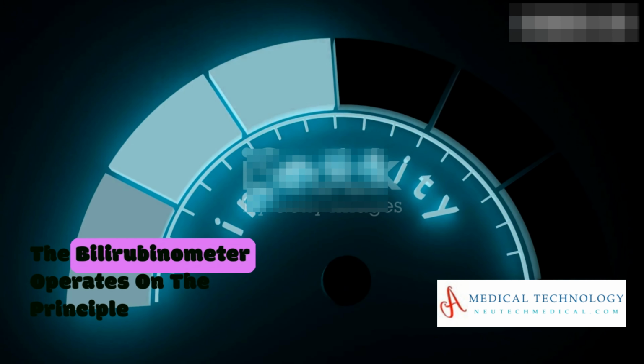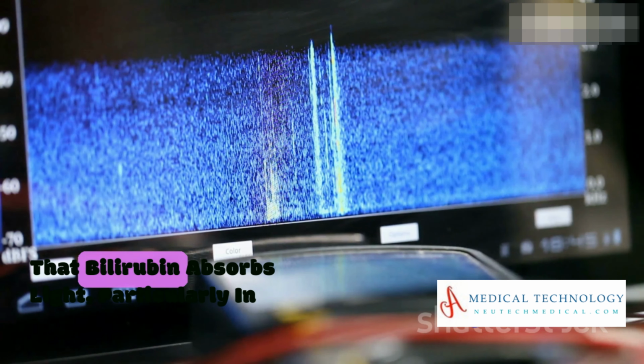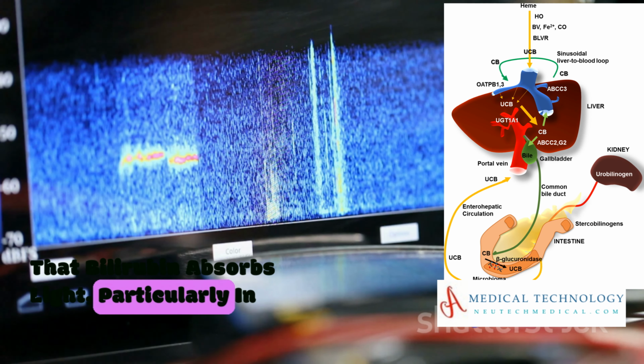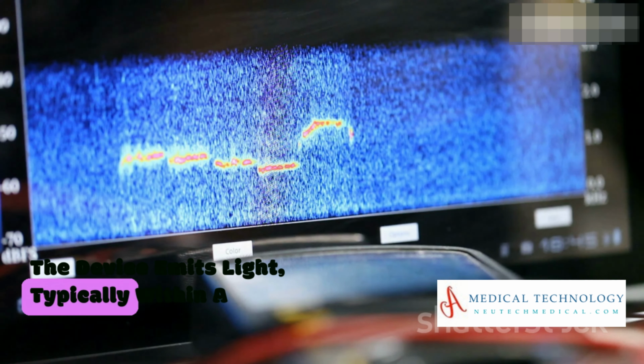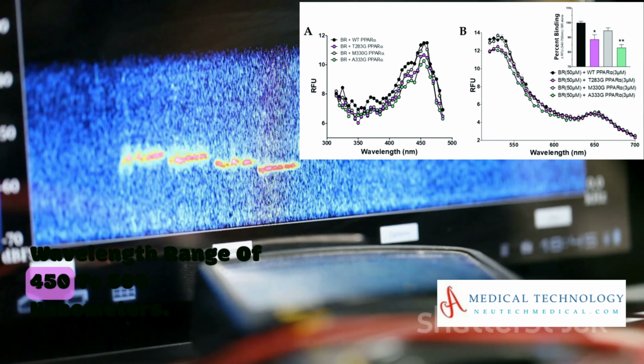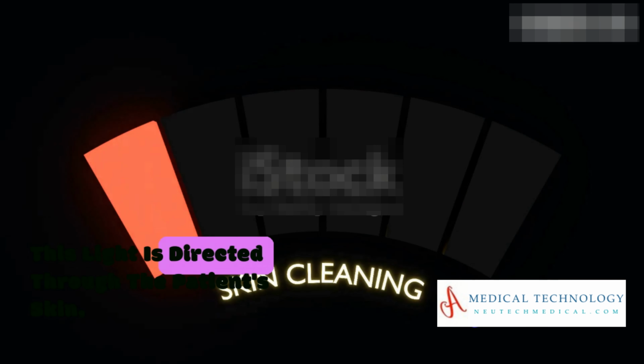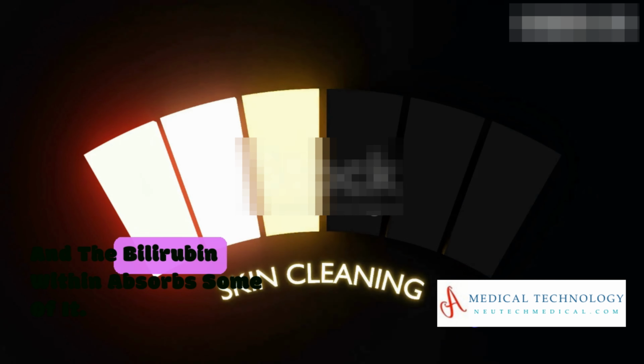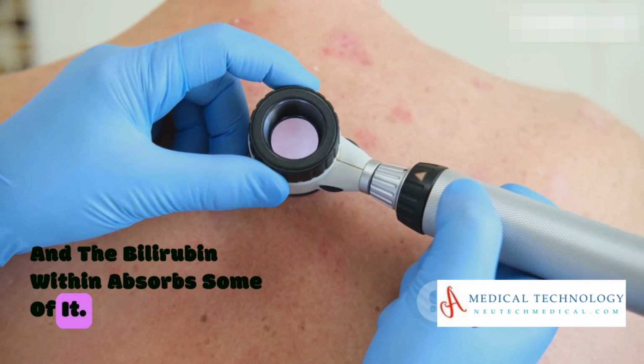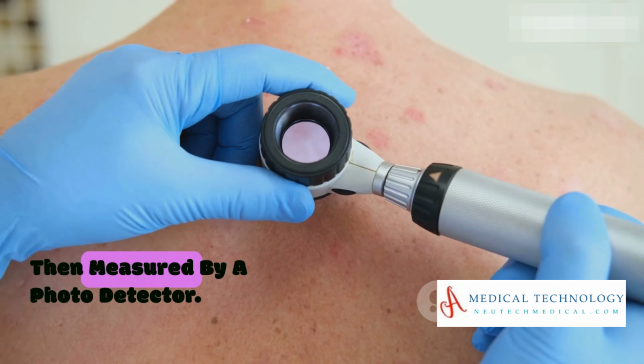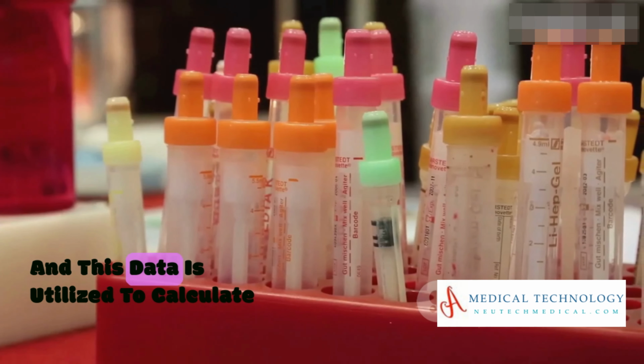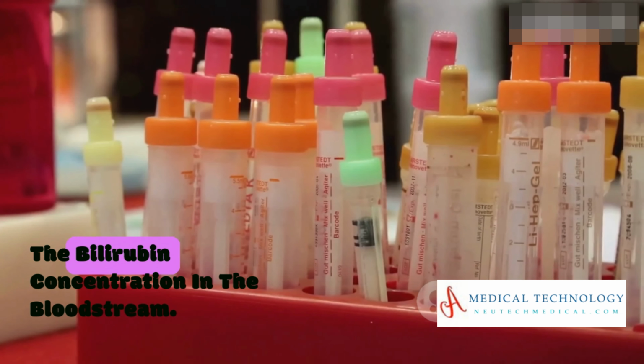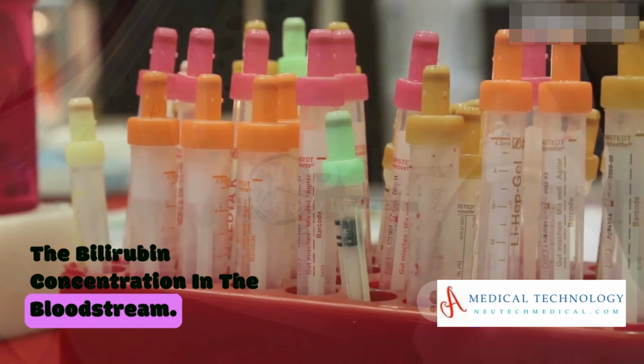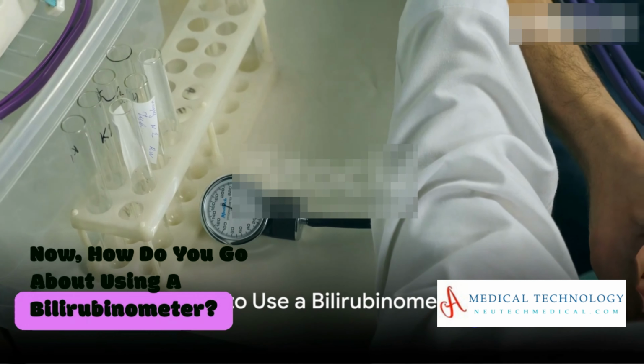The bilirubinometer operates on the principle that bilirubin absorbs light, particularly in the blue-green spectrum. The device emits light, typically within a wavelength range of 450 to 500 nanometers. This light is directed through the patient's skin, and the bilirubin within absorbs some of it. The amount of absorbed light is then measured by a photodetector, and this data is utilized to calculate the bilirubin concentration in the bloodstream. Now, how do you go about using a bilirubinometer?